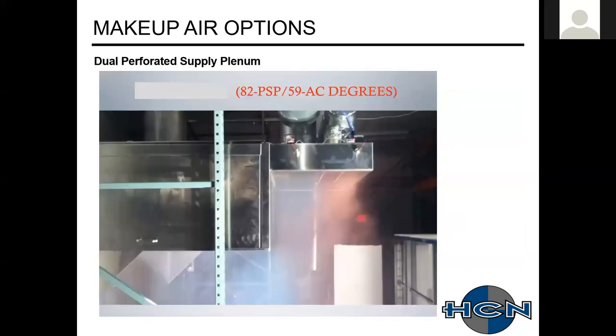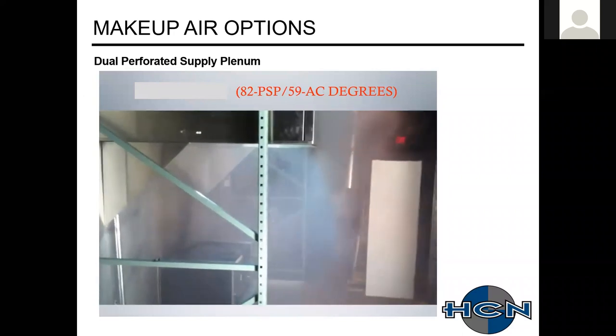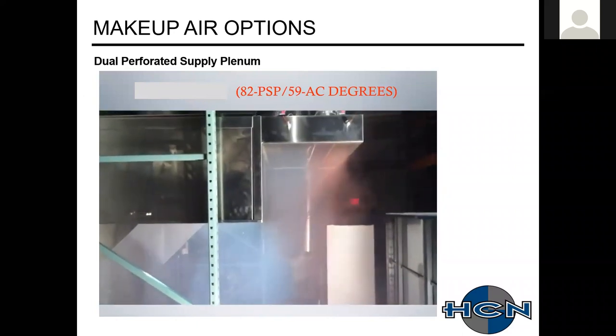To solve that kind of problem, a couple manufacturers have come out with a dual plenum configuration to minimize the diffusion of that makeup air into the space, while also providing some spot cooling for those cooking staff utilizing the rooftop units in the space. Here's a video of that. The red is from the rooftop unit, the blue you can see mixing. That red rooftop air is creating a curtain, which is what we want, because we don't want any of that makeup air to diffuse into the space.